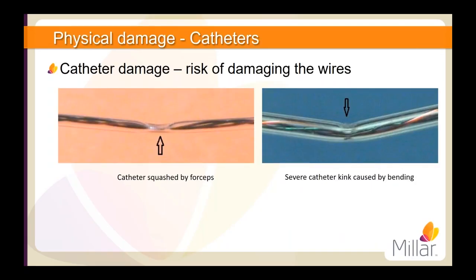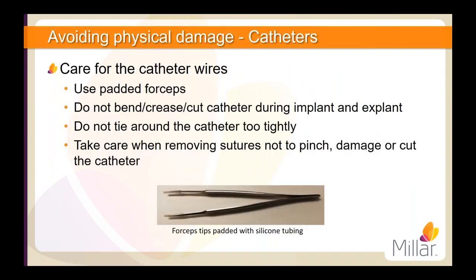Now, aside from the sensors, the catheters themselves can also be damaged by rough handling. If the catheter tubing is squashed or kinked by sharp bending, then the internal wires may suffer damage. Unfortunately, it's not possible for us to repair such damage, so it is important to avoid it. Careful handling is critical to avoid catheter damage. If you are going to use forceps to handle your catheter, then the tips should be padded with silicone tubing. This will allow you to grip the catheter with the forceps, but it will reduce the damage to the catheter if it is squeezed too hard.